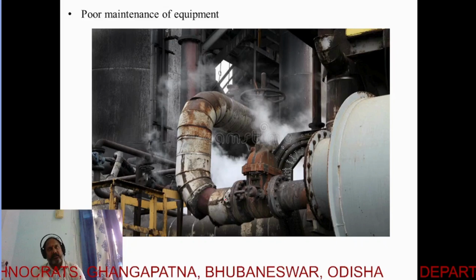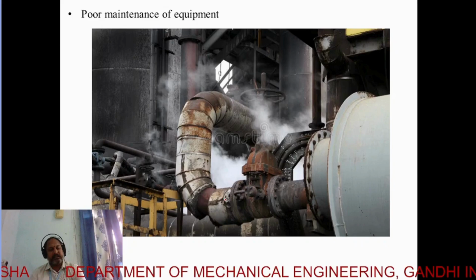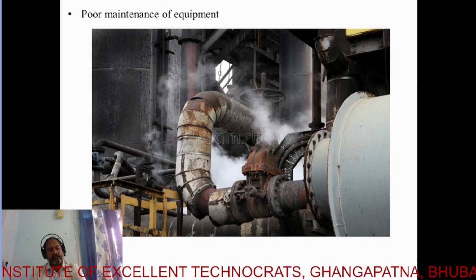The recommendations: it will be better to immediately conduct leak isolation and repair it, and it's better to implement steam trap testing and joint inspection protocols, apply protective coatings, and try to install insulation jackets wherever required, and train the persons who are working around this industrial piping system.